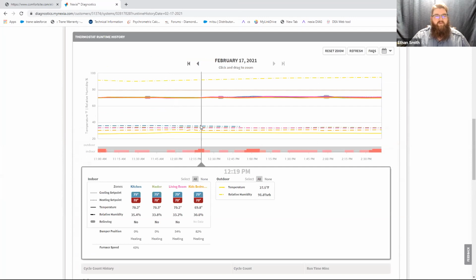Okay. But we can see that anytime the kid's bedroom is the only zone calling, he has a little bit of an excess air problem, because you can come down here in the bottom left and see that damper position is at 25%. And you see that the lines are all a little swollen right up here. That means we're getting some relief in those situations. However, if we come over here, like right here, we're seeing that the living room zone is calling. So it's opened up that damper to 54%, which is minimum, matching my airflow for that zone. There it is, it'll open a little more.